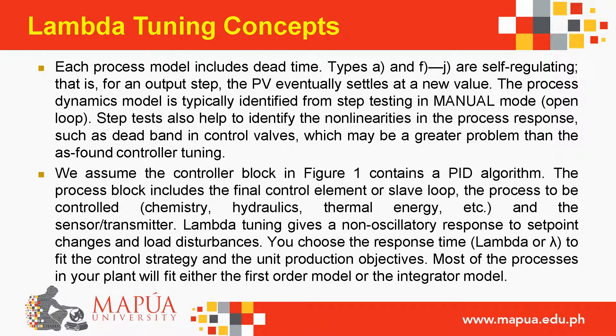Each process model includes dead time. Types A and F through J are self-regulating — for an output step, the PV eventually settles at a new value. The process dynamics model is typically identified from step testing in manual mode. Step tests also help identify nonlinearities such as dead band in control valves, which may be a greater problem than the controller tuning itself.